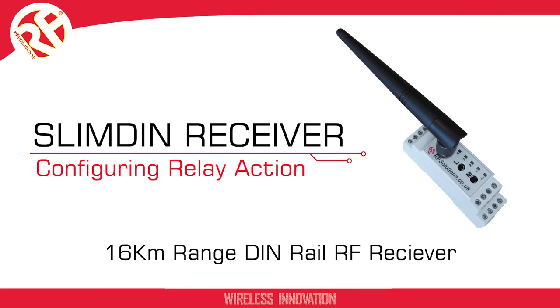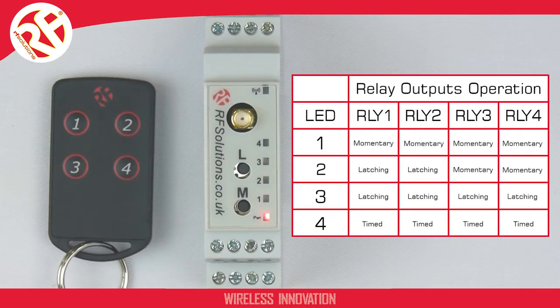This video shows how to configure the relay action on the SlimDIN receiver. The SlimDIN receiver has four relays, and each can be set to operate in one of four different modes. Mode 1 is all momentary action across all four relays. Mode 2 is latching on relays 1 and 2, and momentary on relays 3 and 4. Mode 3 is all latching across all four relays, and mode 4 is all timed.